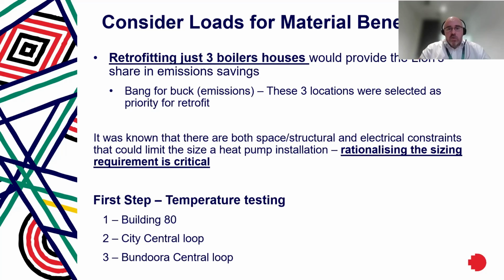So first thing we needed to do was test for temperatures. Heat pumps, as you know, don't like responding at 80 degrees with 20-degree delta on the flow temperature. So we wanted to try and rationalize that if possible to open up our design options for the different heat pumps that were commercially available. So we looked at building 80 in the city, the city central thermal loop, which addresses most of the buildings in the main city campus, and the Bundoora central thermal loop as well.